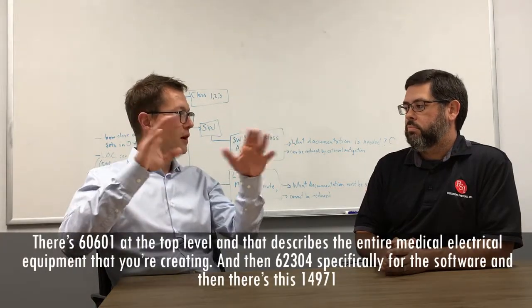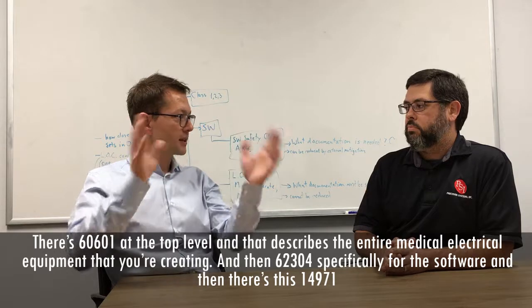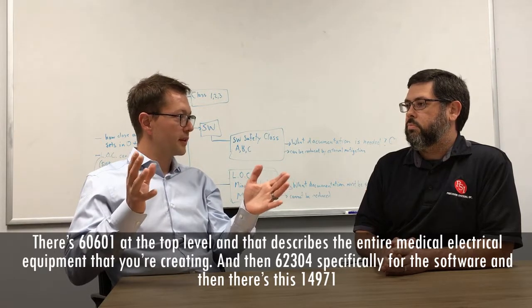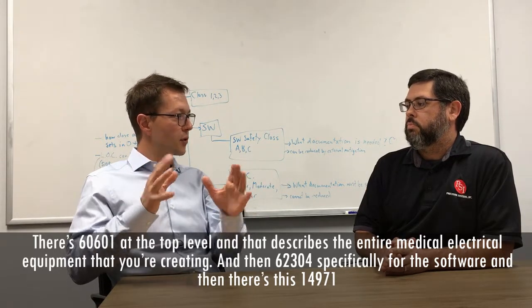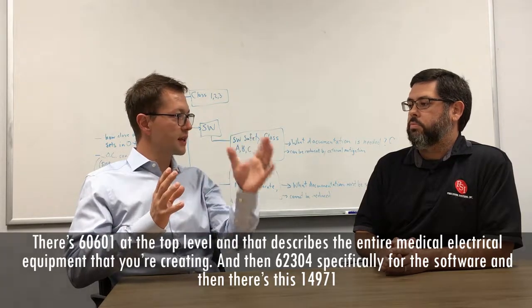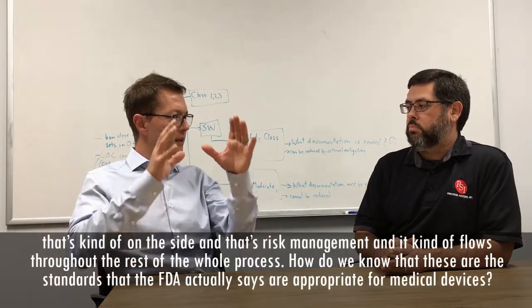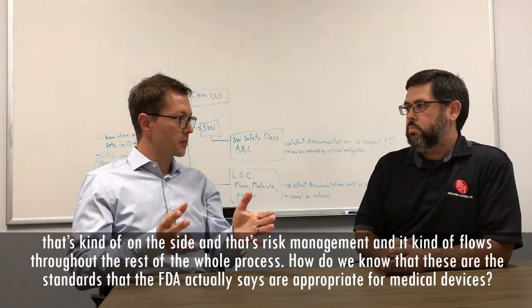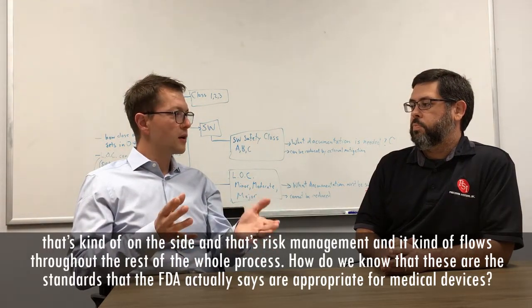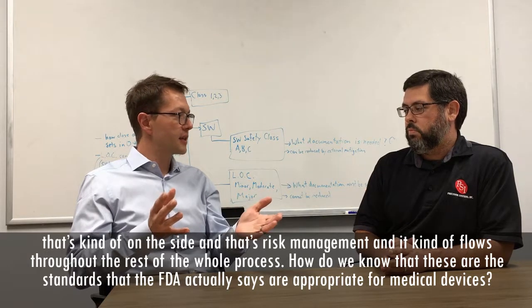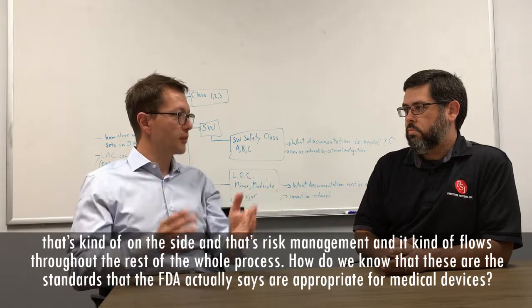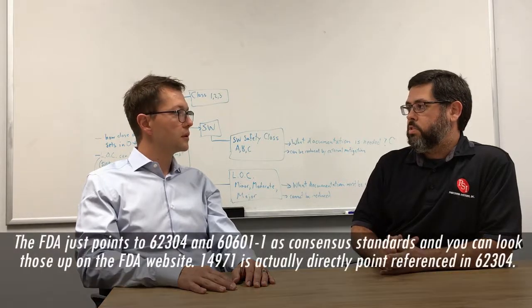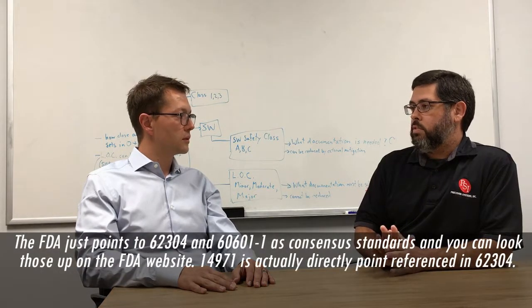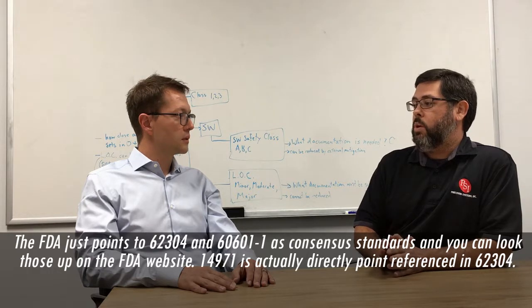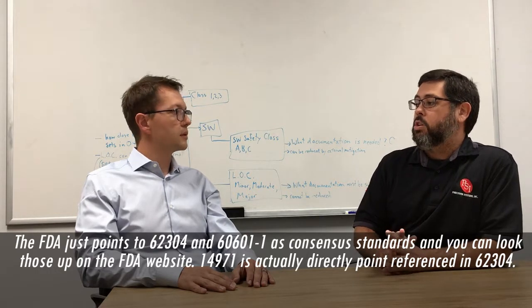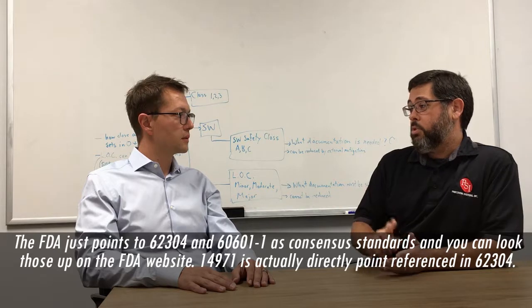There's 60601 at the top level, and that describes the entire medical electrical equipment that you're creating, and then 62304 specifically for the software, and then there's this 14971 that's kind of on the side, and that's risk management, and it flows through the whole rest of the process. How do we know that these are the standards that the FDA actually says are appropriate for medical devices? The FDA just points to 62304 and 60601-1 as consensus standards, and you can look those up on the FDA website.